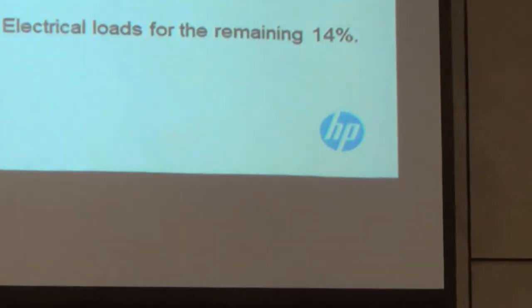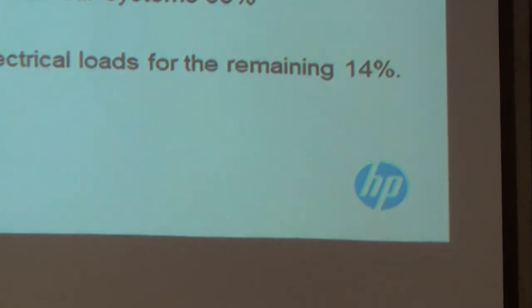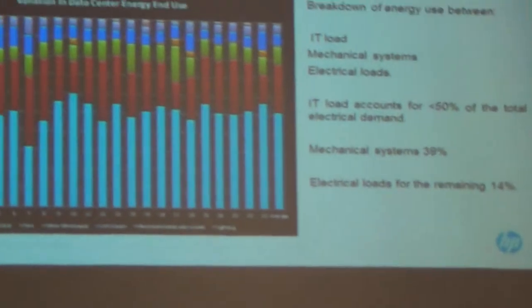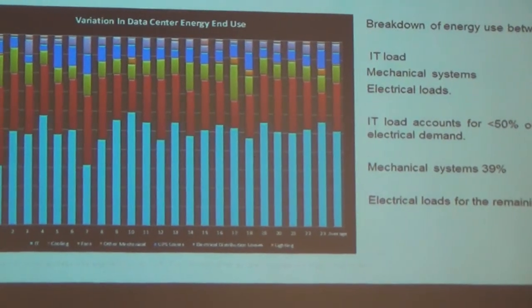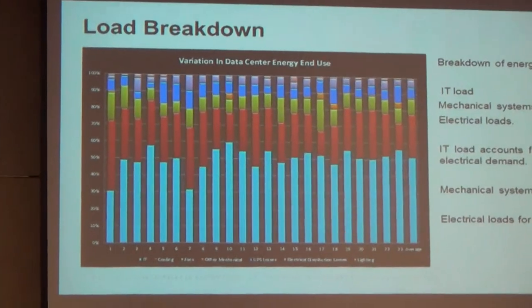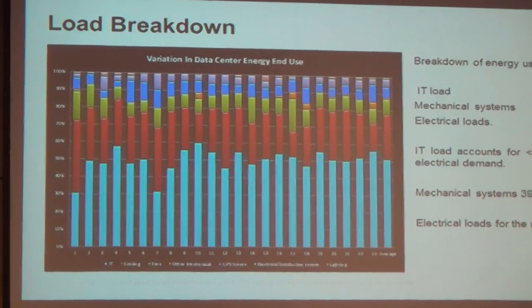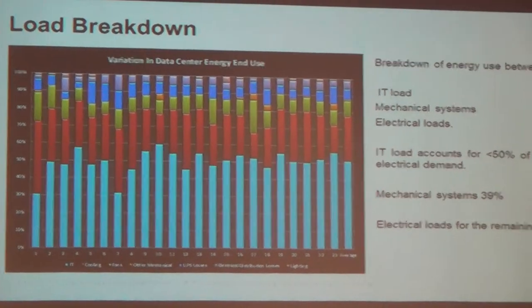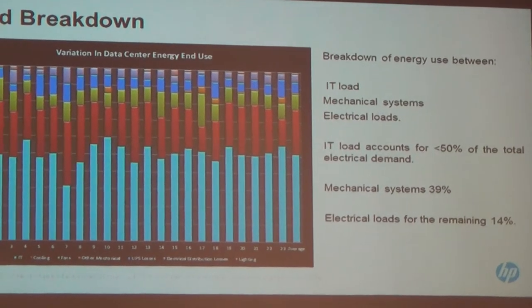We have IT technology now where our servers can operate at 35 degrees centigrade without any problem whatsoever. HP actually have a data center research facility in Mexico, and there is no cool water, cool air - it operates on pure fresh air. The outside temperature is 35, 40, 45 degrees C, and the servers in there are working quite happily. It's you that needs the temperature modification, not the servers.